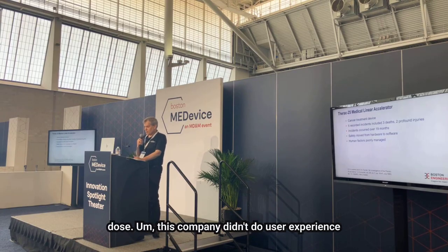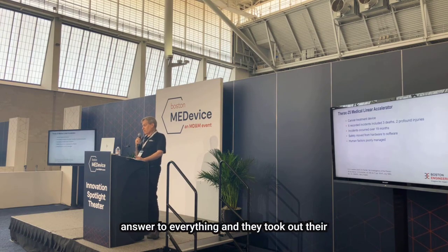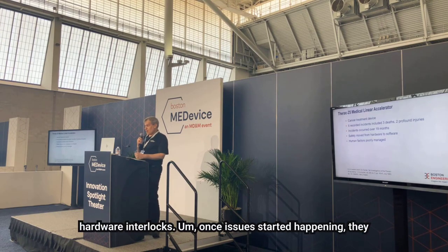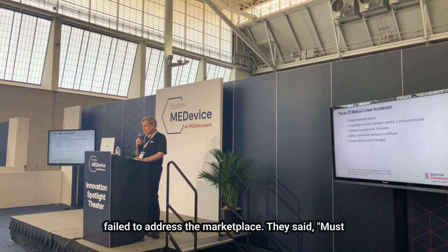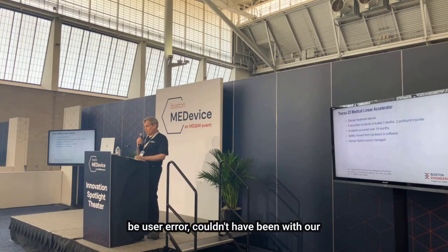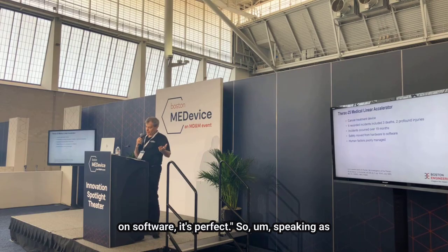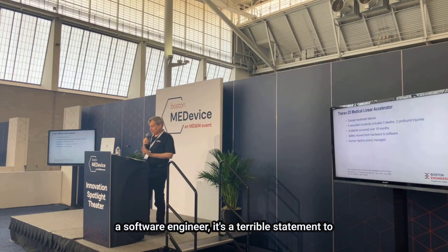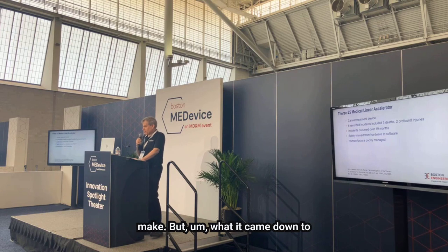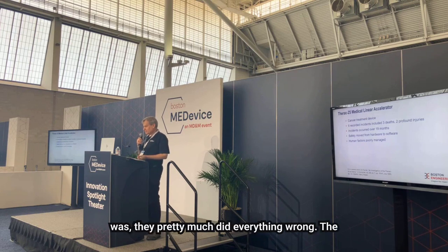This company didn't do user experience or human factors. They decided software was the answer to everything, and they took out their hardware interlocks. Once issues started happening, they failed to address the marketplace. They said, must be user error, couldn't have been with our system. There's nothing wrong with our system. It runs on software, it's perfect. So, speaking as a software engineer, it's a terrible statement to make. But what it came down to was they pretty much did everything wrong.